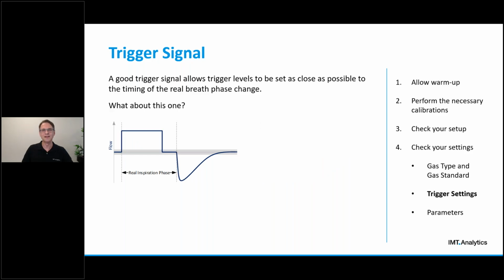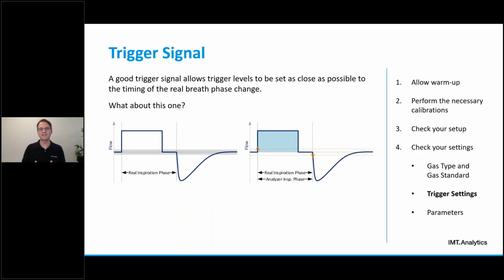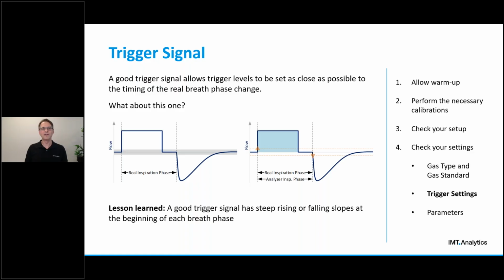Last example, how about this one? So this one is actually perfect, right? Because here we have very steep rising and falling edges or slopes of the signal, right where our real breath transitions are, which makes it easy to set trigger settings perfectly in sync with the reality. So our lessons learned from these three waveforms you've seen: a good trigger signal has a steep rising or falling edge or slope at the beginning of each breath phase.